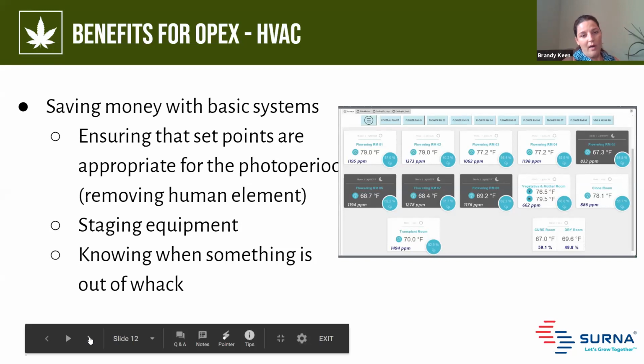Depending on how much equipment you have in the room, and how many fan coils, air handlers, and compressors, you can also stage equipment on. For instance, say I have a 50-ton load in this room, achieved with four 15-ton packaged rooftop units for a bit of redundancy. Instead of having them all come on when we call for cooling and all turn off when we don't need it anymore, maybe we turn on 2 for stage 1, a third for stage 2, and the fourth only at stage 3. That means I'm not using more than I need at a given time.